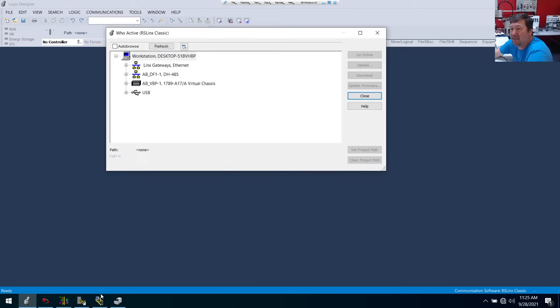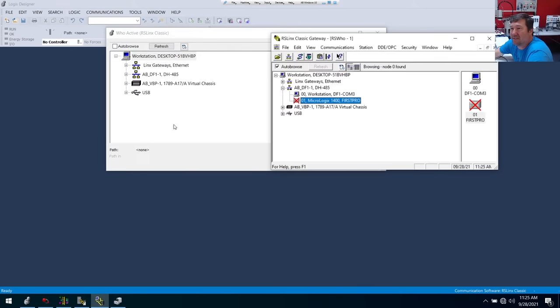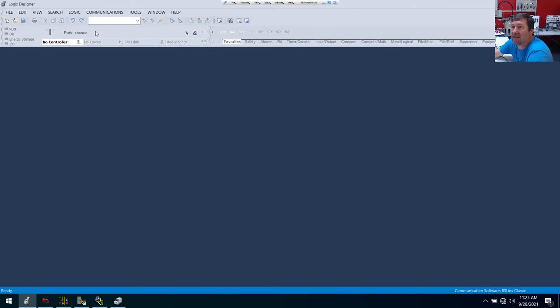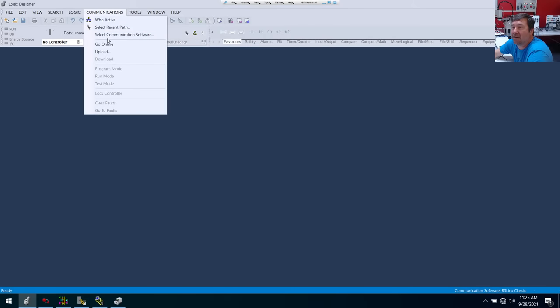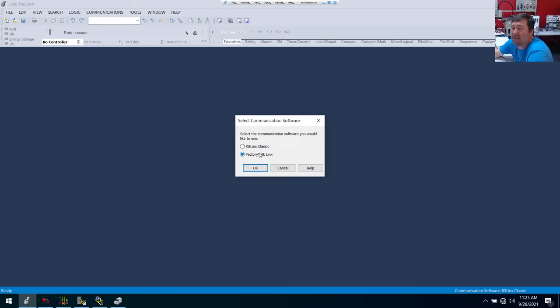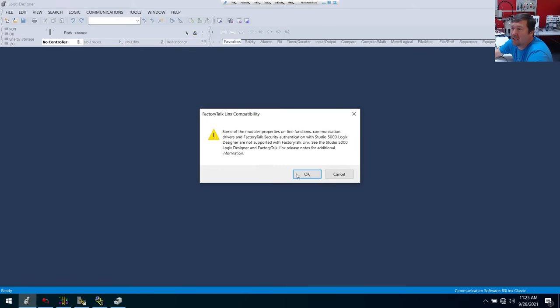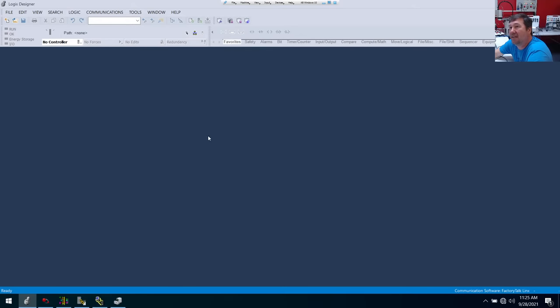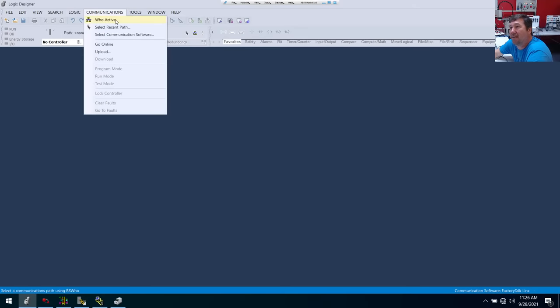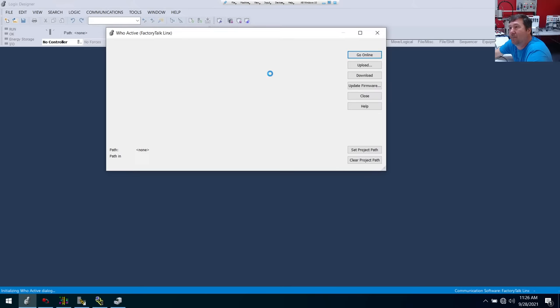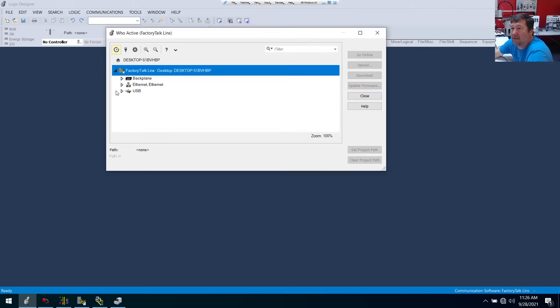We do have the USB, but that is based off of this RSLinx. So we're going to switch communication softwares — we're going to select FactoryTalk Linx. Really, unless I'm going over serial, I leave mine on Factory Talk. But notice this warning right here — this is an important warning. It's telling you, hey, we don't have everything in FactoryTalk Linx that you're used to. I wish they'd kind of say go to RSLinx if you can't find it. And now we're going to go to Who Active.